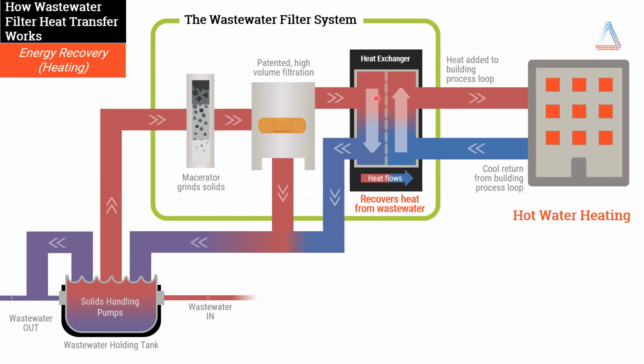So this is, of course, where the energy is transferred across the wall of the heat exchanger from the wastewater source and into that geofield, sending back a much warmer temperature into the field that can then be used for all of its downstream purposes. And then we return a cooler temperature back to the wastewater source once that energy has been absorbed. So typically the heat exchangers are sized roughly for a 10-degree Fahrenheit delta. There's a bunch of different ways that you can look at this: higher, lower deltas, different approach values, in order to make sure that you're feeding enough energy into the loop as you need.